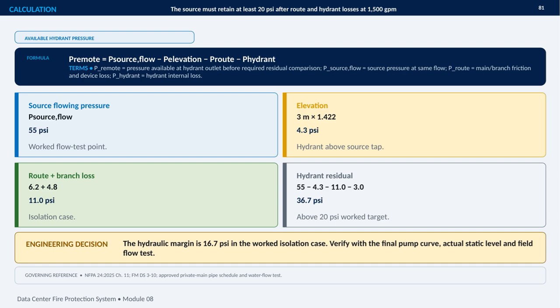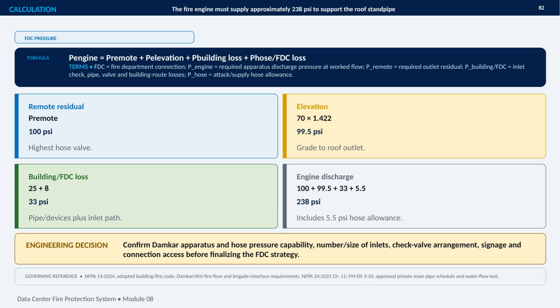and water flow test. This calculation determines the fire engine discharge pressure needed to support the roof standpipe. The governing formula adds 4 components: the required residual pressure at the remote outlet, elevation pressure, building and FDC losses, and the hose or FDC allowance.